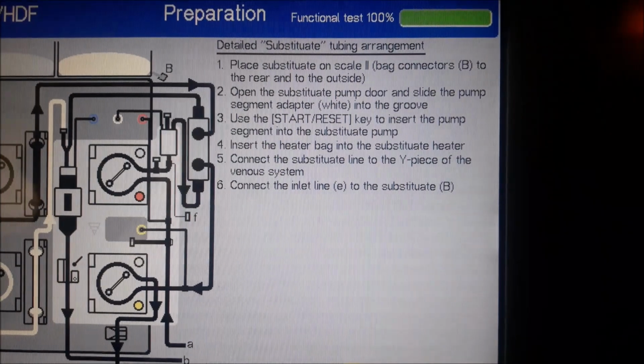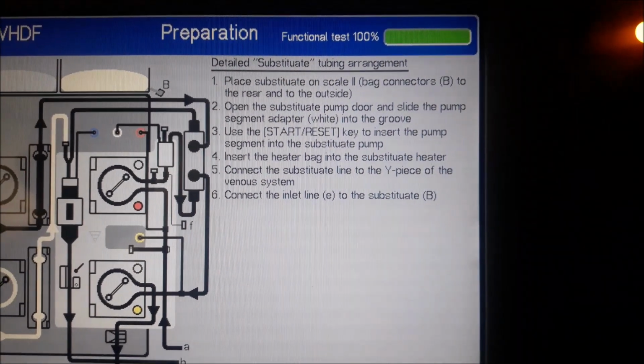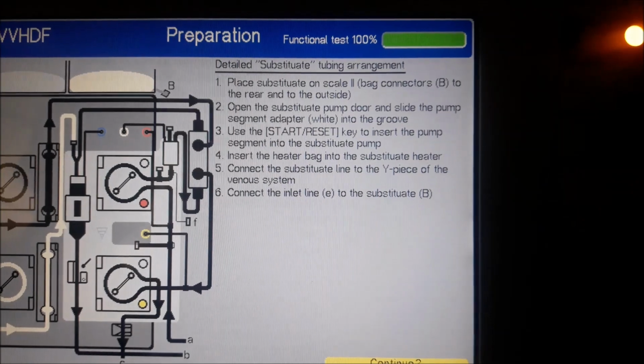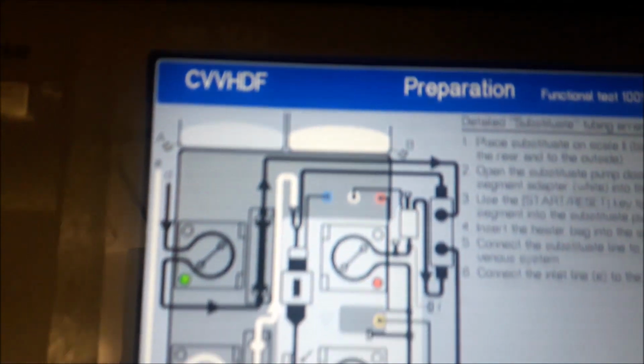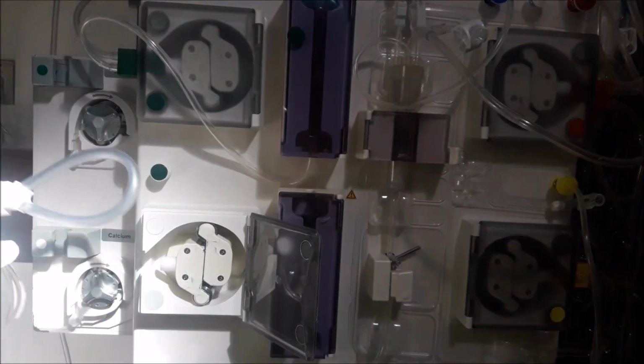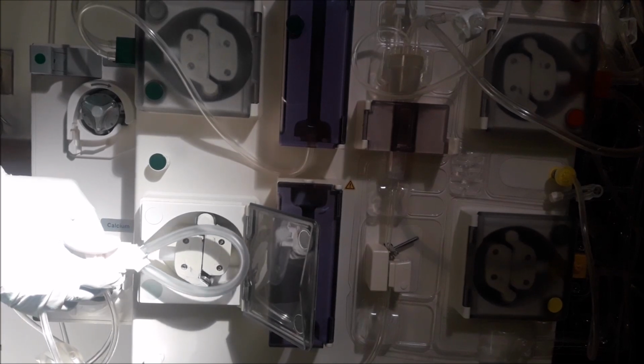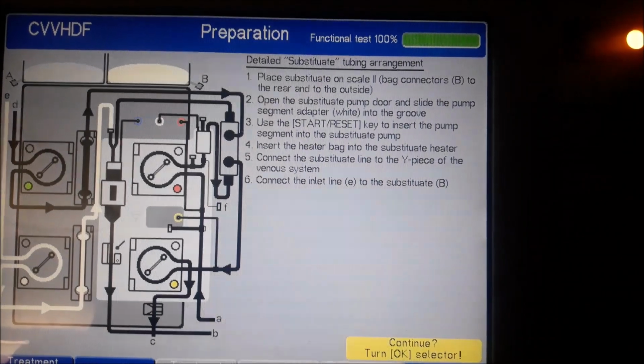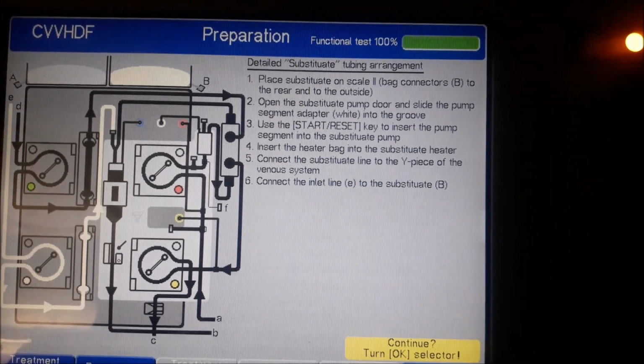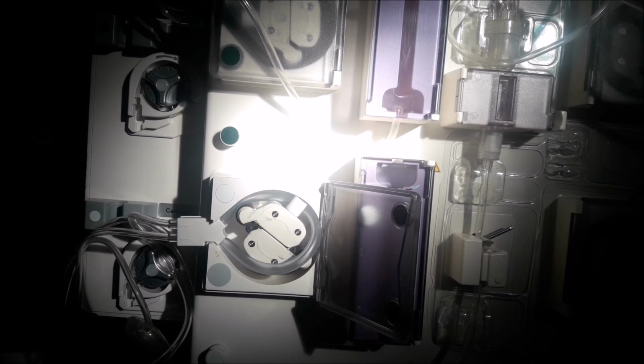Point 2 is open the substitute pump door and slide the pump segment adapter, white, into the groove. Now we will open the door of the substitute pump and insert the segment of tubing into the groove. Use the start reset key to insert the pump segment into the substitute pump until the tubing are fixed into the substitute pump. As you see, tubing are fixed.